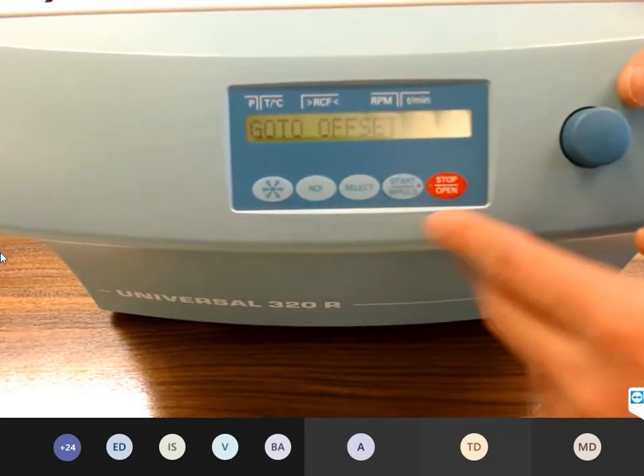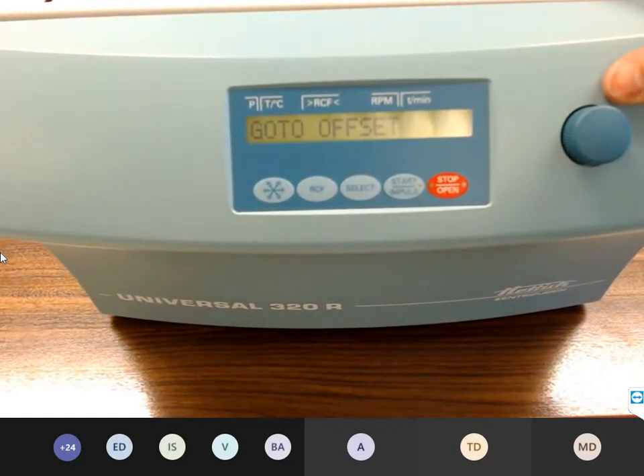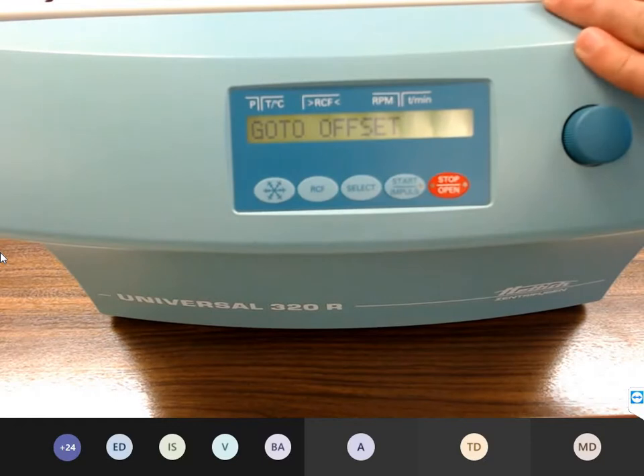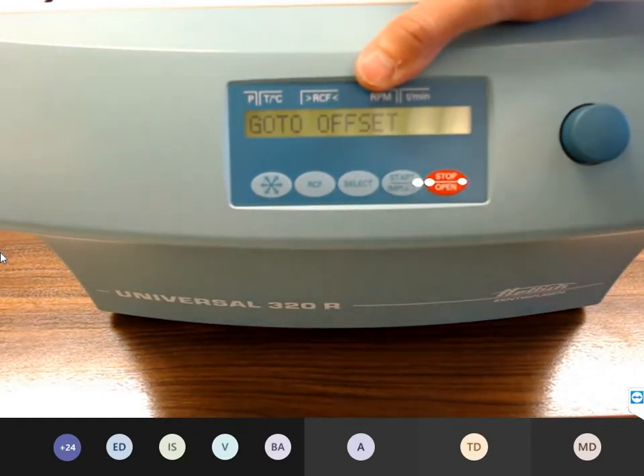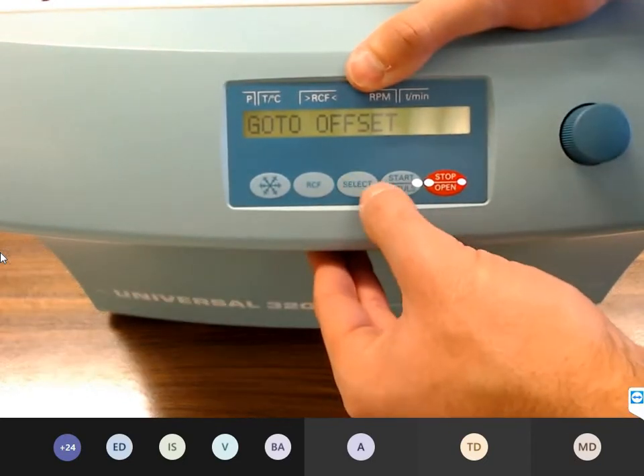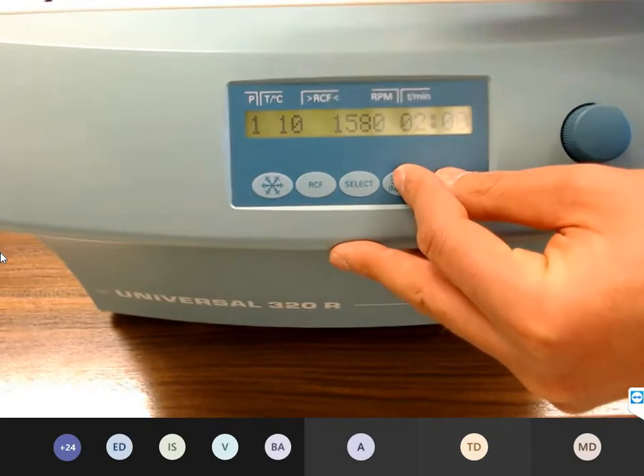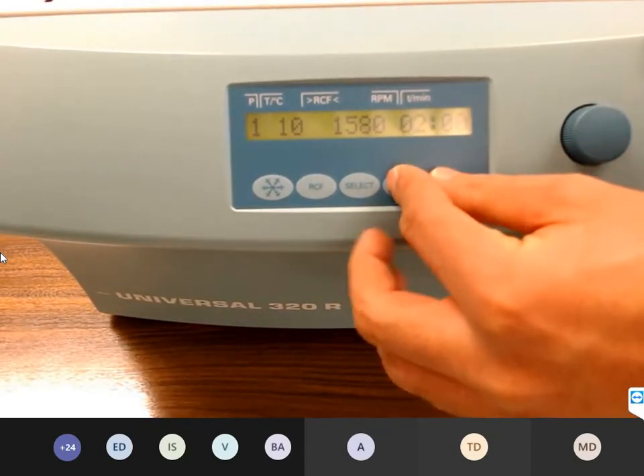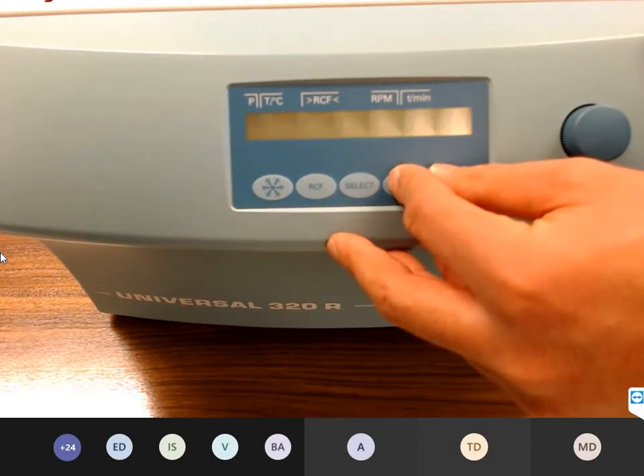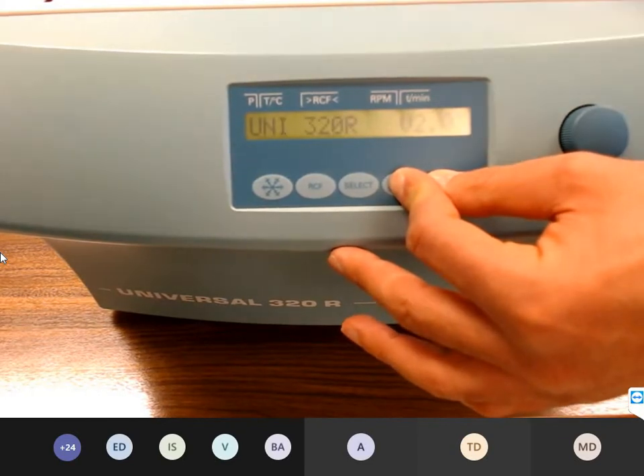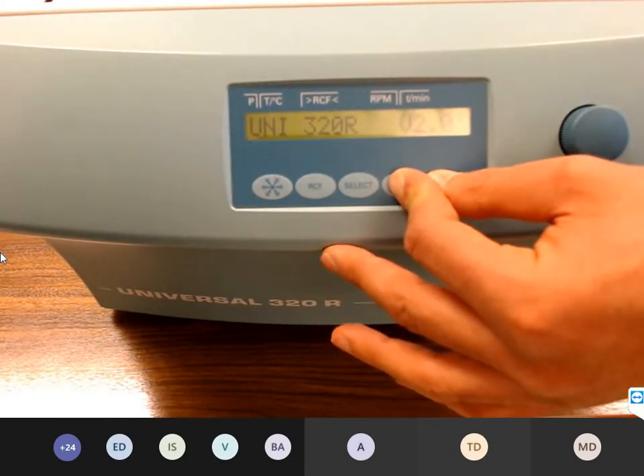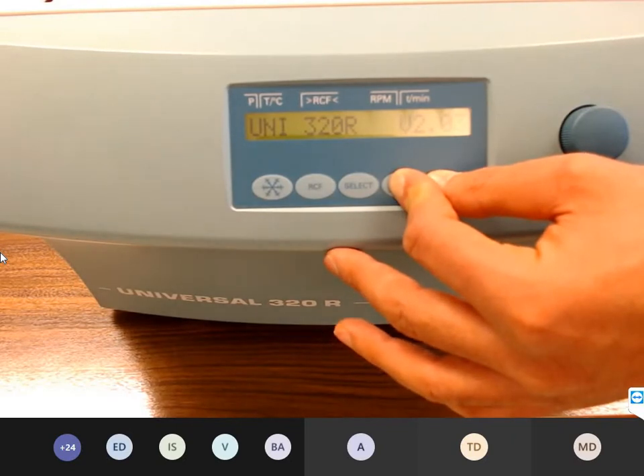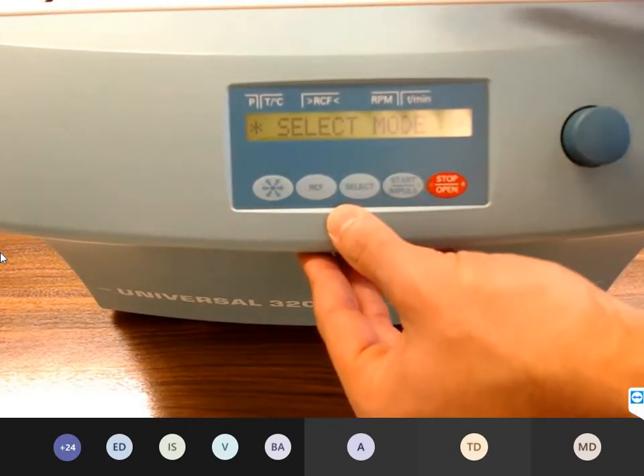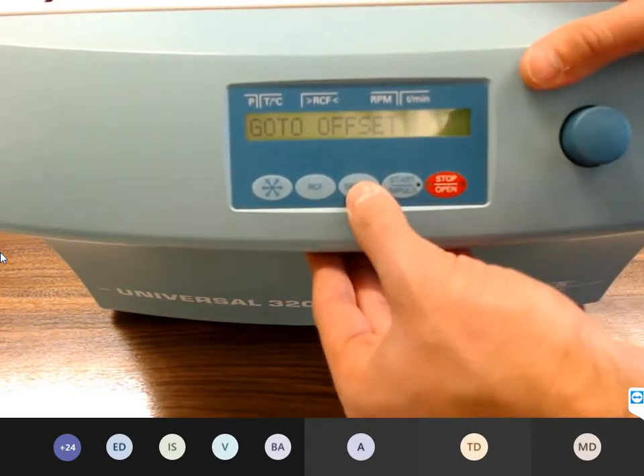In the select menu, we can set the offset values. Very important: if you change the control board or one of the temperature sensors, you have to set the offset values again. Oh, I was so slow. What is the offset menu? This is the difference between the real temperature and the measuring temperature. If you don't press a key for 8 seconds, it switches again to the standard mode.